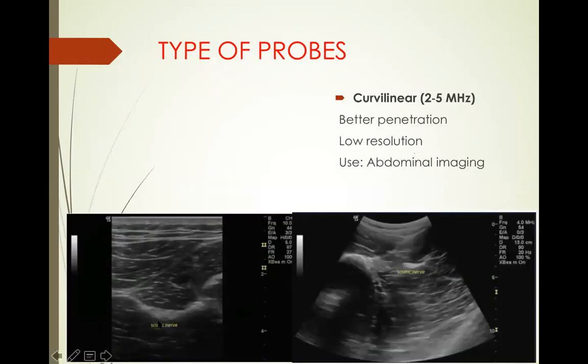This is the picture of the linear probe, and this is the picture of the curvilinear probe. With the curvilinear probe, there is better penetration, meaning we can see deeper structures, but with lower resolution. The picture is not as clear as that of the linear probe.